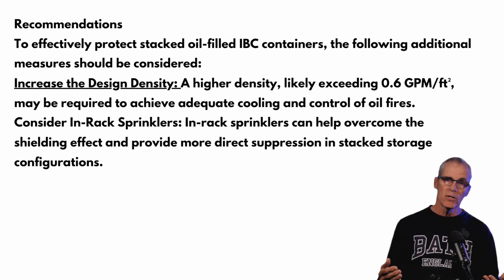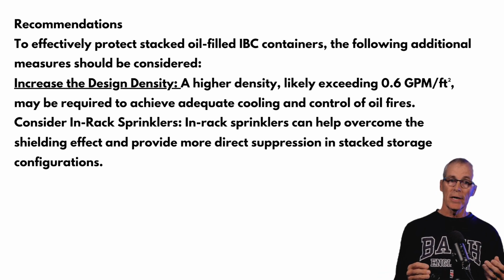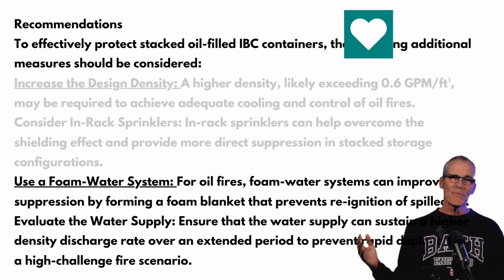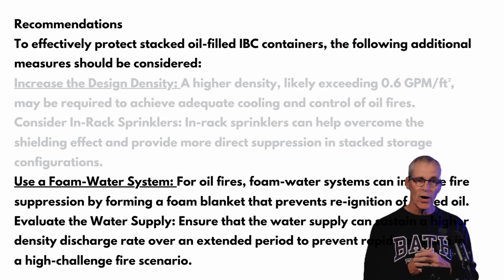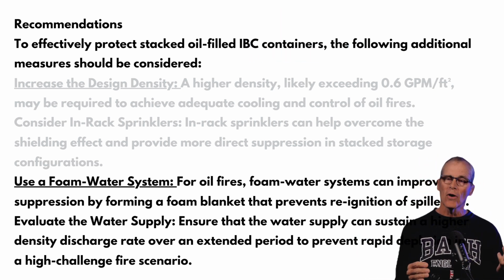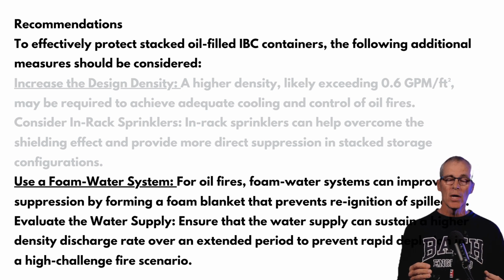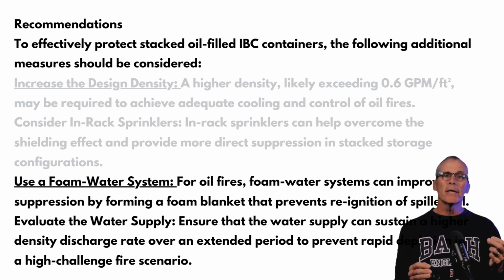So it then took it a step further, and it said that I can either increase the density, which is what all of us thought, and we were immediately saying, well, we need a bigger water supply and bigger tanks, and that was the first thing. But it reminded us, this is AI, helpful, right? Use foam water. We don't have to always use more water. Foam water is great on flammable liquid fire. So that was a great idea that came up.